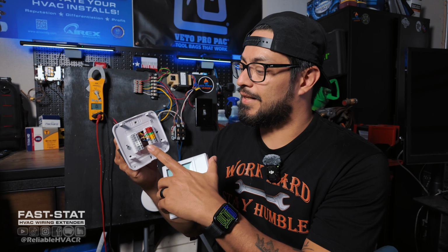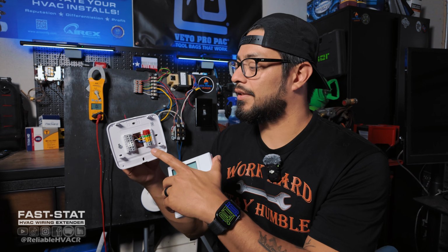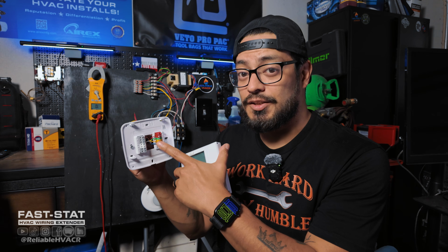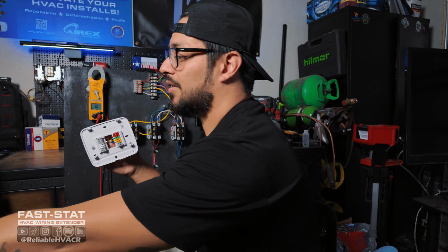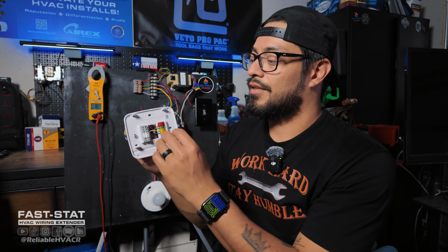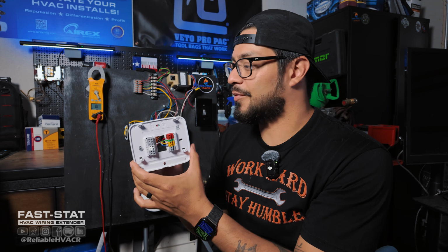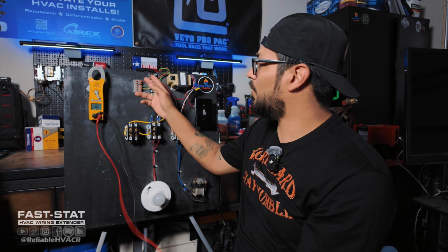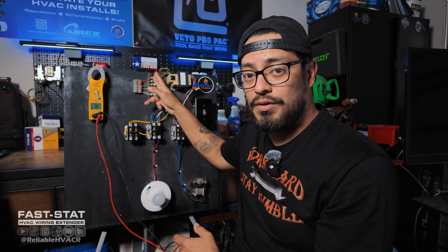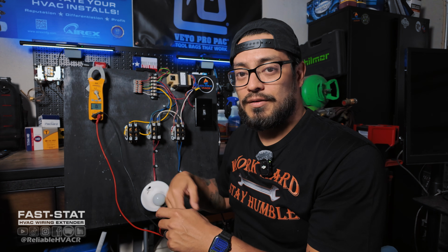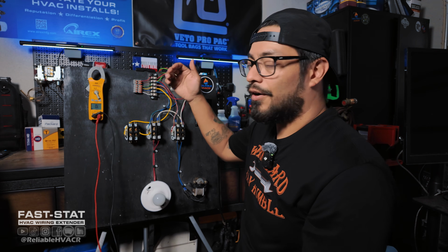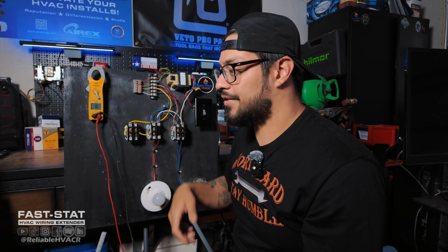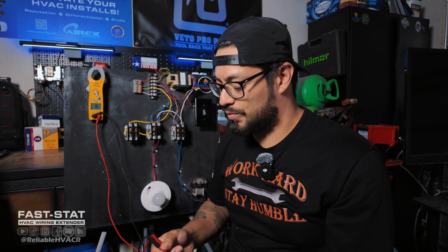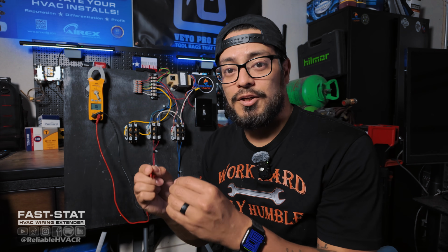And by removing that, technically all of these have their own terminal and they're not going to be touching, because this is what makes them touch or close contact with. So I'll remove that at the thermostat, the faceplate, make sure that that's not calling or anything like that. And then I'll also take off the wiring from either the control board or the terminal block. So then remove your R, common, green, all that stuff, and make sure you have the power off at this point if you're checking for something grounded.